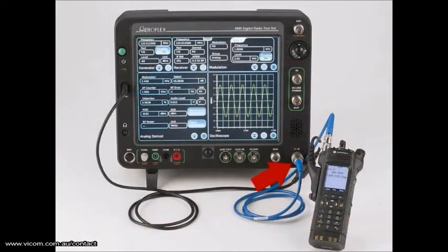The first step in the AutoTest procedure is to connect the radio's antenna port to the 8800 TR port. The radio's data I/O is connected to an 8800 USB connector. If a mobile radio is selected for test, the power supply of the radio can be connected through a shunt to the 8800 DMM input. This enables PA bias to be aligned.